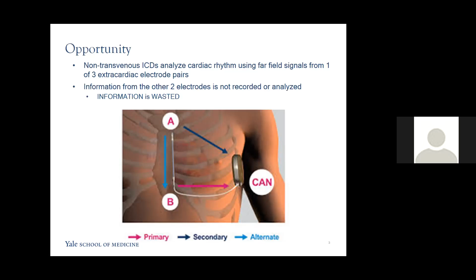So I propose, and Jim and I have been working on this, a vector-based approach where far field signals from 3 electrode pairs are transformed into a vector cardiogram that is able to represent depolarization in much more exquisite detail than the standard far field representation from a single electrode pair. This schematic here is actually of Medtronic's extravascular ICD, which is similar to Boston Scientific's design, except Medtronic's design has the coil actually under the sternum and the anterior mediastinum. However, the relationship of the electrode pairs is similar.